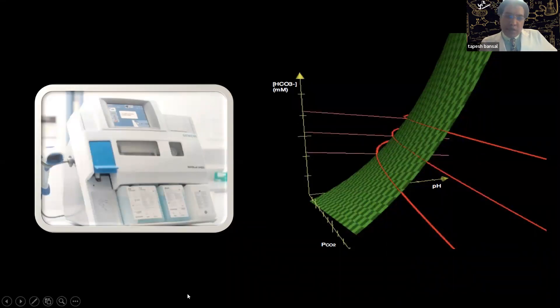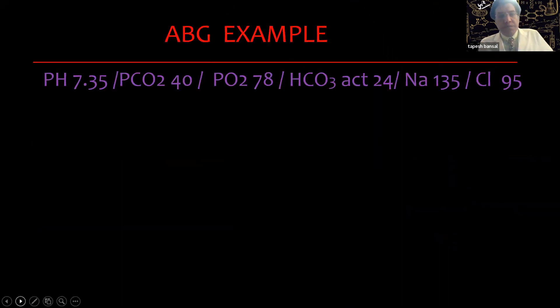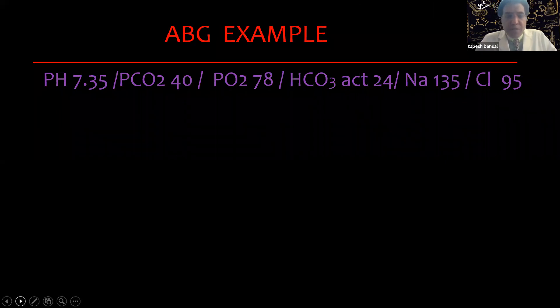From that period we have moved on to the most sophisticated and automated blood gas analyzers. There are lots of machines — some are really good, some are not — and they need adequate calibration. This is very important because sometimes they're not calibrated and your ABG values are haywire. I'll be showing you some examples; many are real, some are made up just to show the concept. Have a look at this ABG and see if it is normal or abnormal.